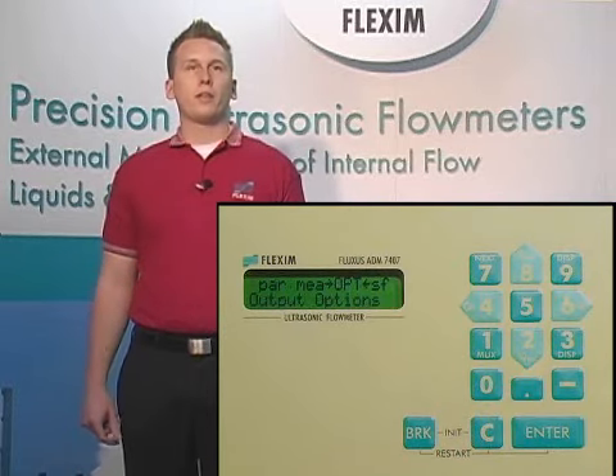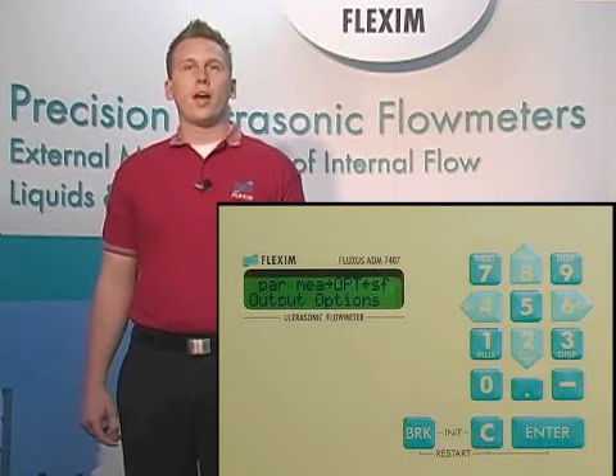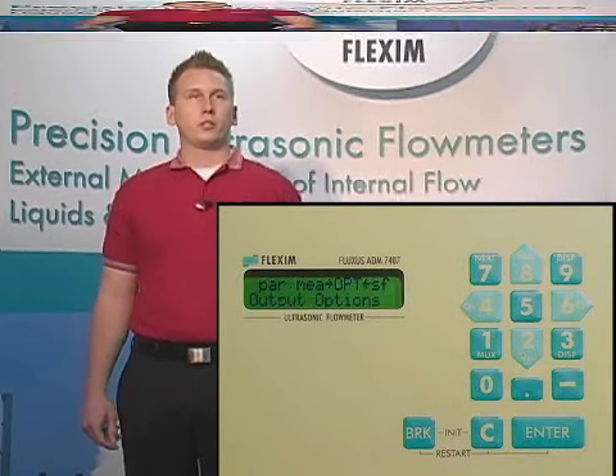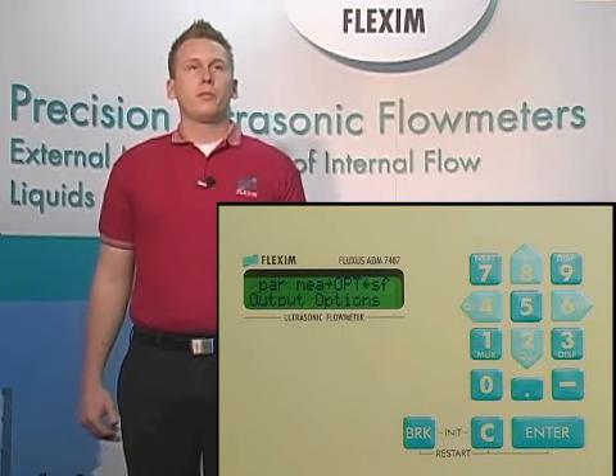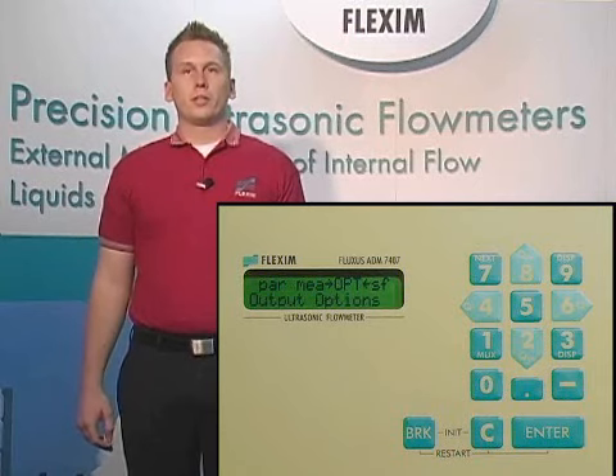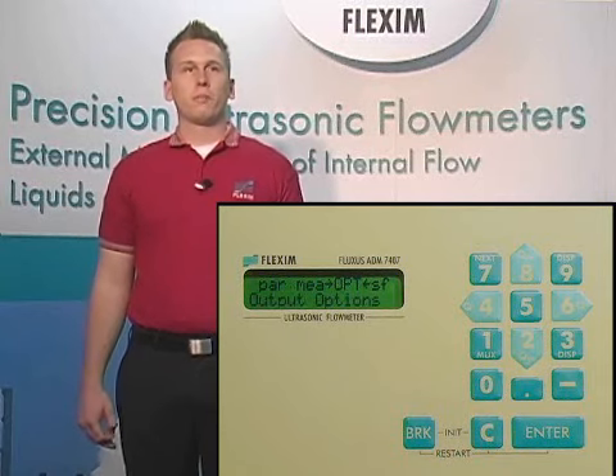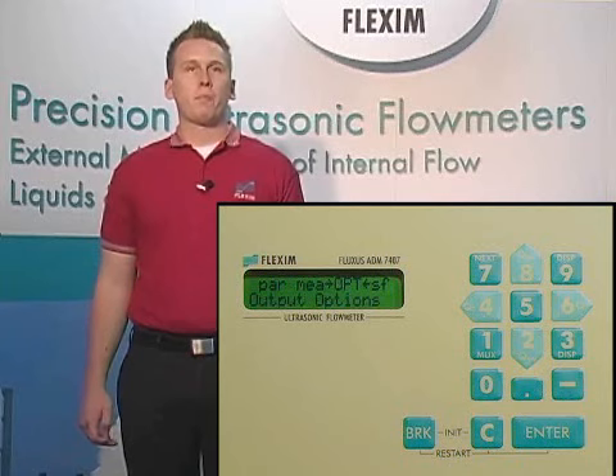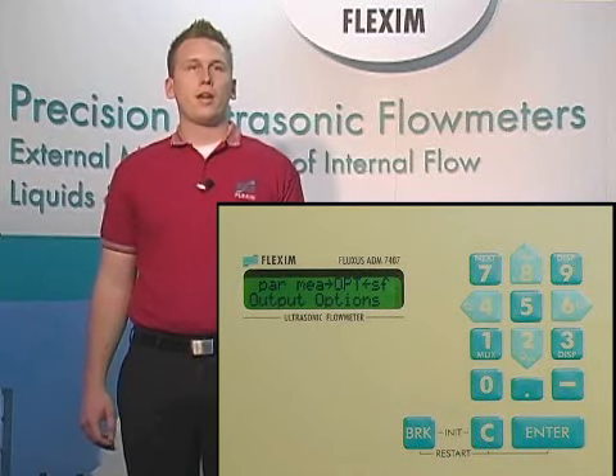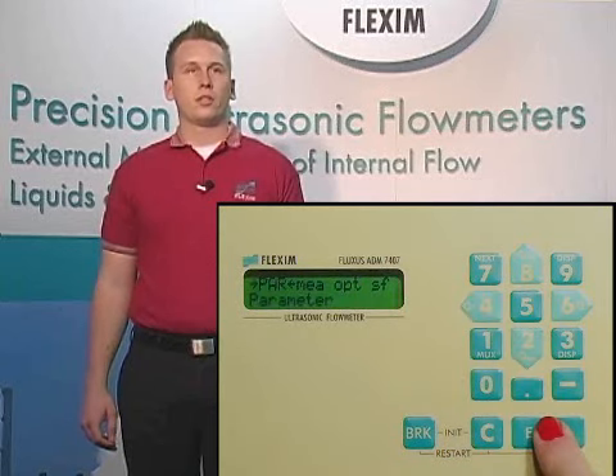Now that we talked about how to use the meter, we should look at how to actually program the meter to take a measurement. The first menu we should look at when setting up a new measurement is the parameters menu. This is where we'll input all the information we have about the pipe, fluid, and liner if it's present. Start by scrolling to PAR for parameters and hit enter.